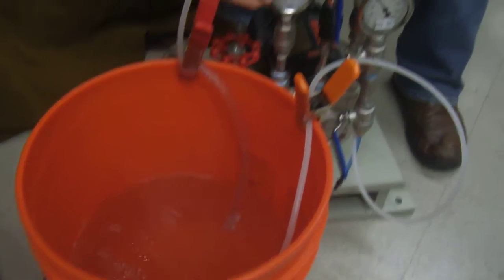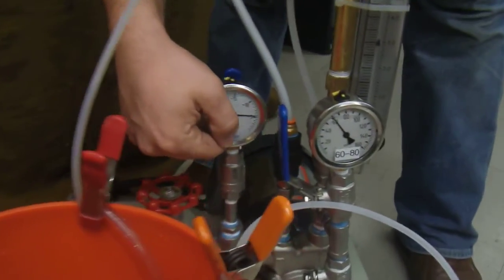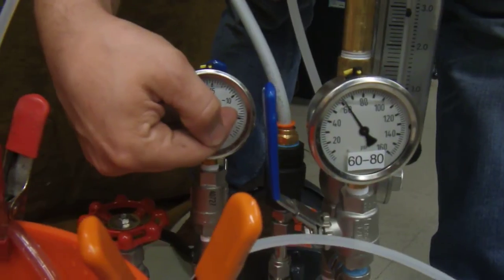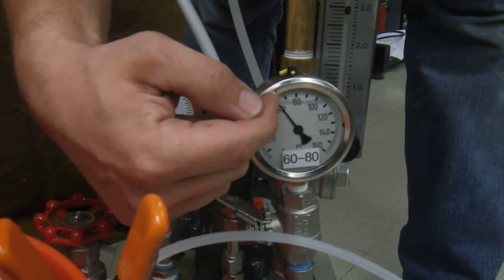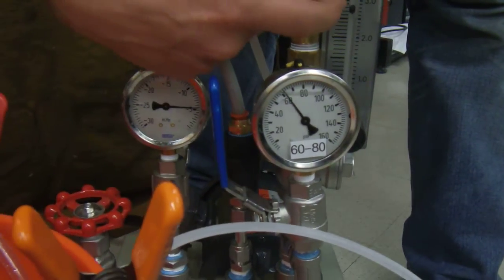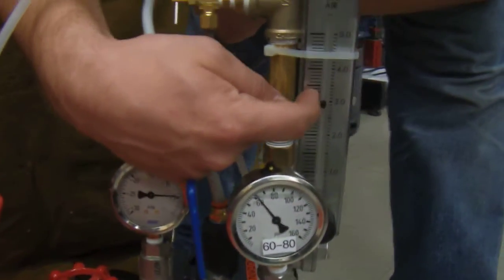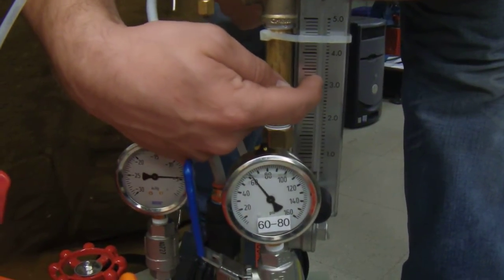So you can see right now that there's about 5 inches of mercury vacuum that's being pulled on the intake of this. And on the output is just over 60 psi. And the air inflow is 3 cubic feet per hour.